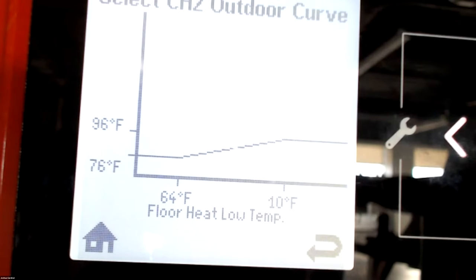The one thing we need to protect, though, is that low temp. So if my CH2 calls, it's only going to go and satisfy this curve. But while CH2 is running, if my CH1 kicks in, boom, I'm going to that hotter curve. It's going to ramp up. And then I'm sending 180 degree water through my radiant. And that's when we have cracked floors, cracked tile, and all that.